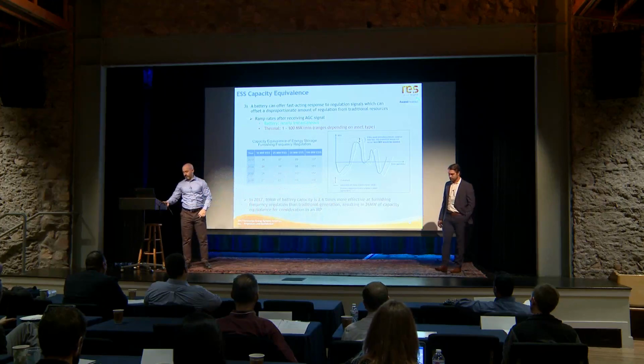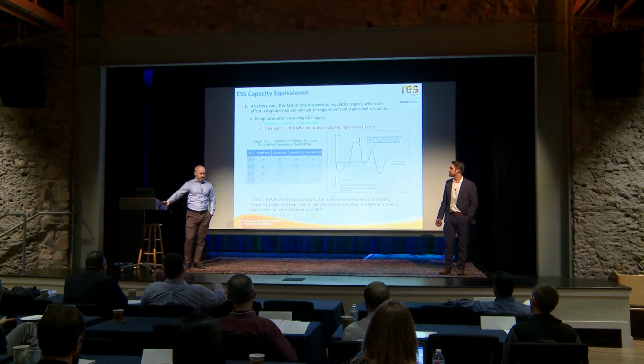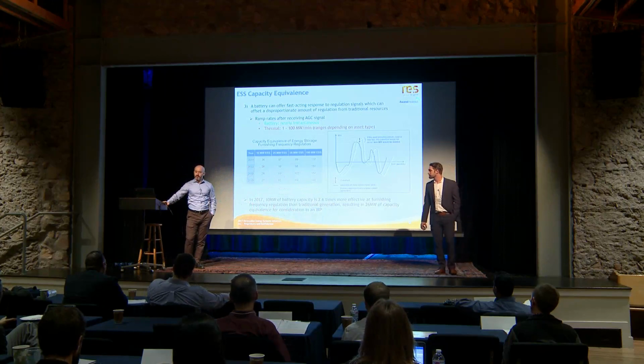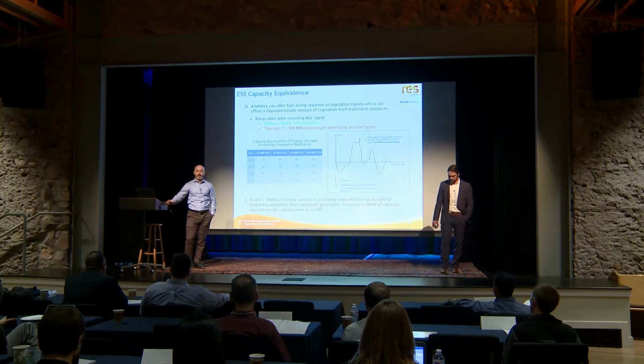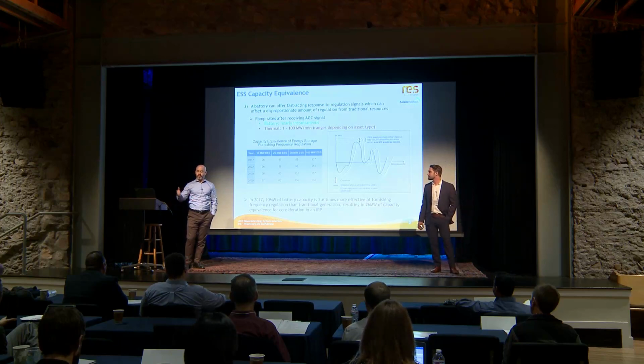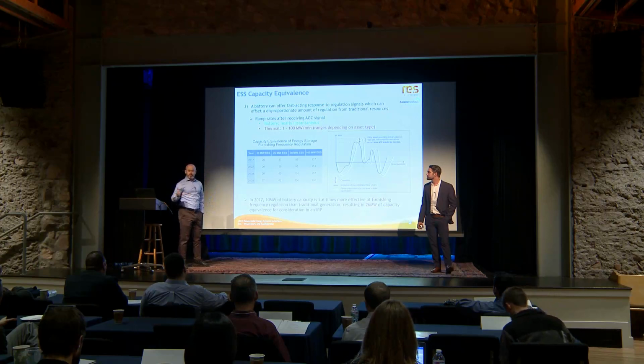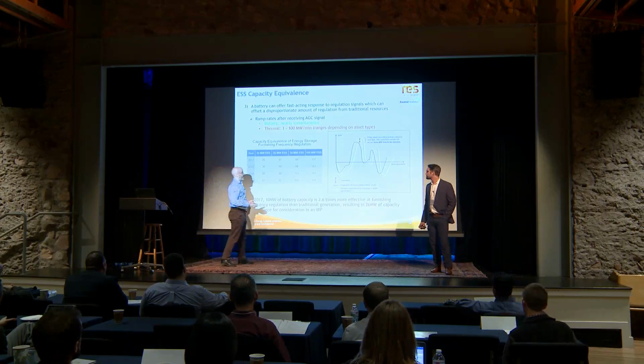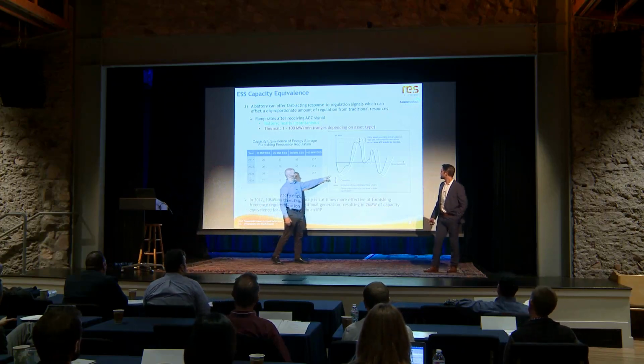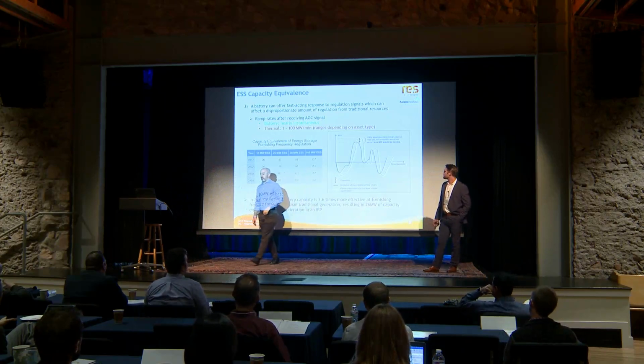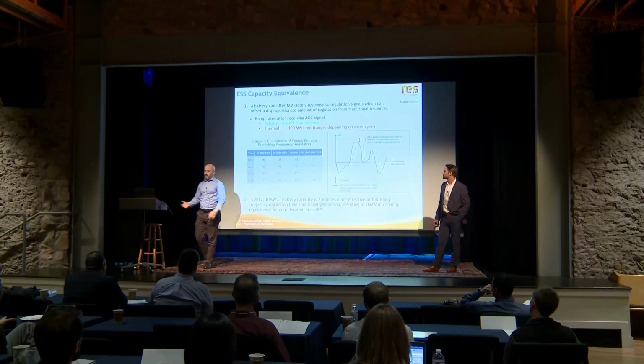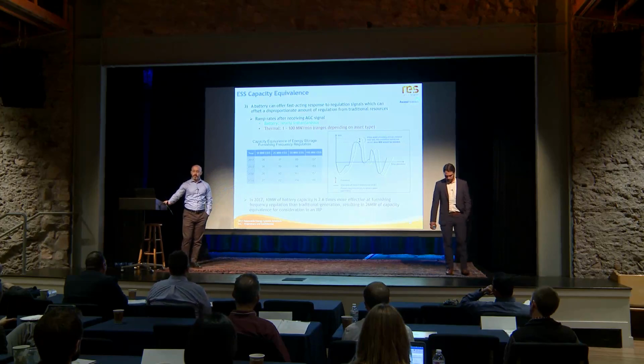One of my first jobs was turning power plants into video games—I built the simulators that train control board operators. I can tell you from experience, there's not just a knob you turn and it goes from 10 to 20. It goes from 10 to 21, to 19, 20 and a half, 19 and a half, 20. We have these limitations at each generator's level where we can't perfectly meet the required signal. But a battery can—it has nearly instantaneous ramp and very fine control on exactly what it can and can't do.